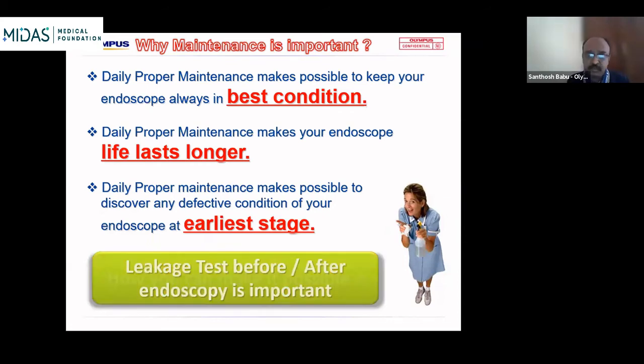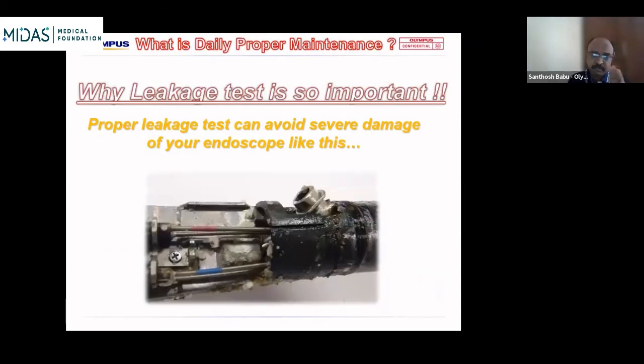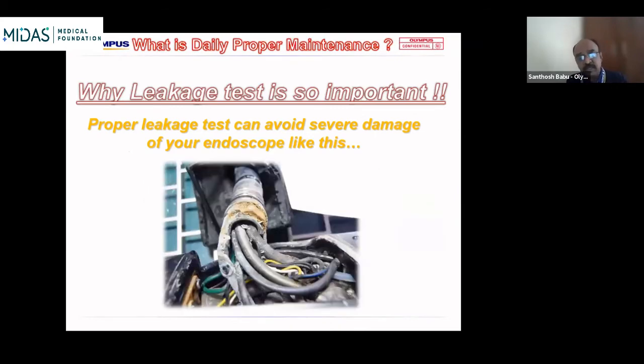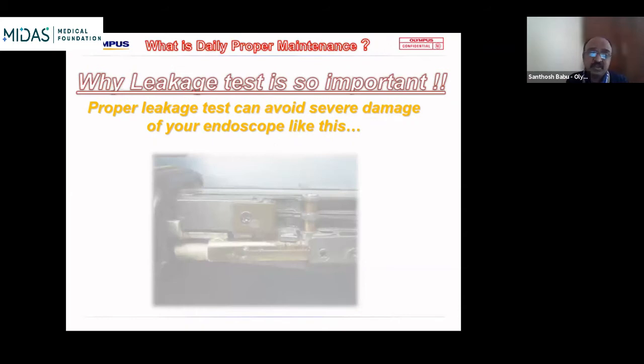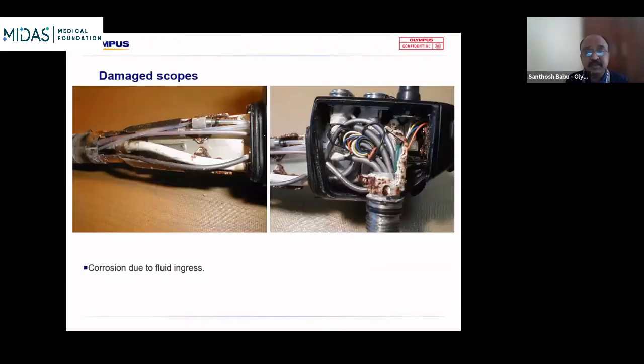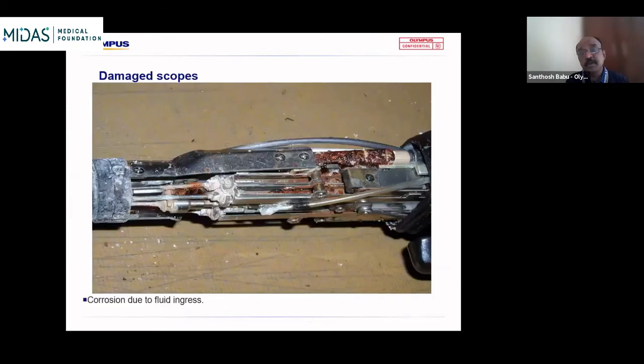How do you make it possible? Leak test. If you don't do a leak test every procedure, which is a mandate, you can get into problems such as these. These are real life photos of scopes that were spoiled. Maybe after 10 or 20 procedures, when you finally find the problem and open up the scope, you find such things, which is too late to save it. It's all about rebuilding the entire endoscope. So please do the leak test.